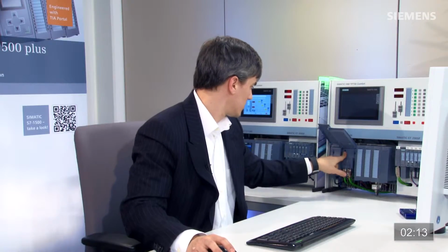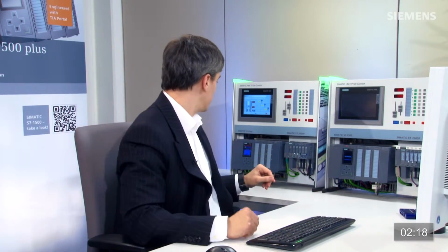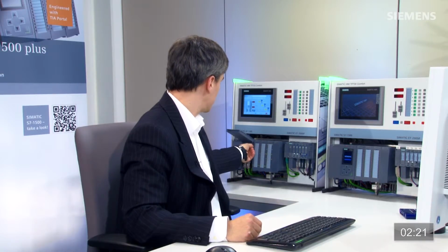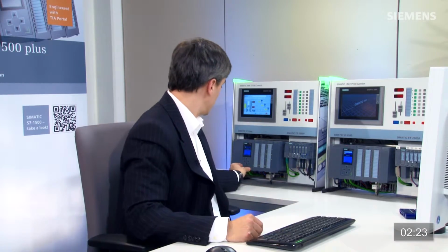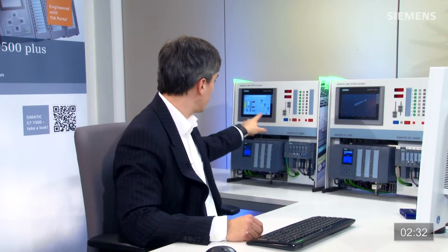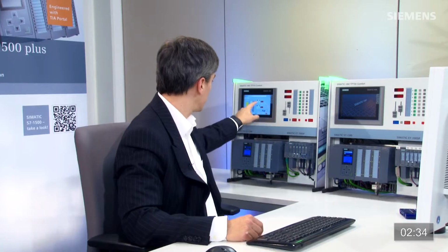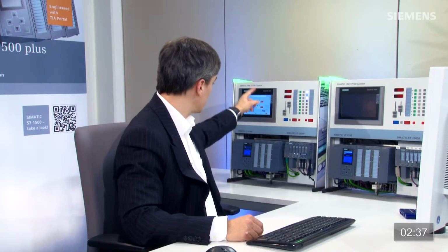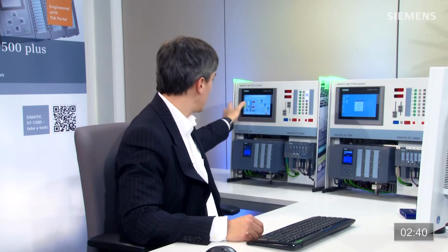All right, so now let's put this in the old existing system and see if it works. Let me power them up. If I go back to the new system, all I have to do is take it down to stop mode and back up to run. You see the hardware configuration is fully accepted and even the code is functioning. If I move the slider up and down, everything functions. I can turn these valves on. And in fact, I can even come over here. I can turn on the mixer. I can turn on the pump. You can see all the LEDs are functioning. Everything from this control system is now fully functional because I actually bound that program to this memory card.